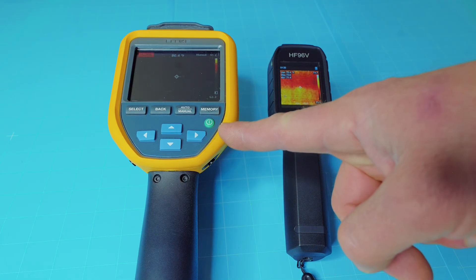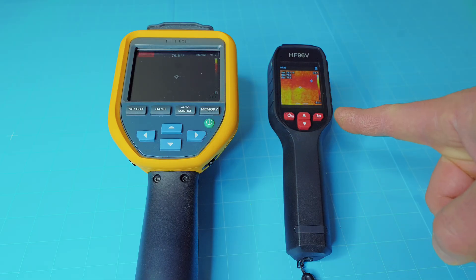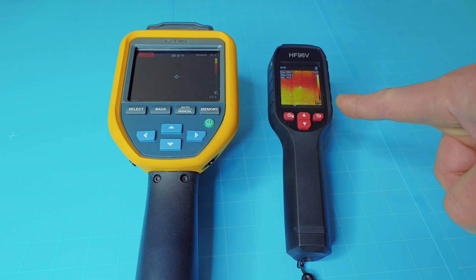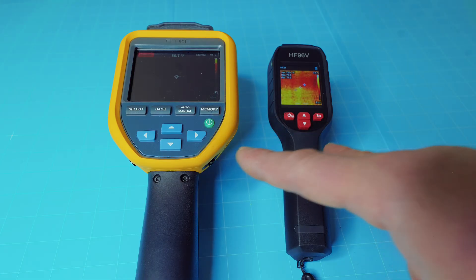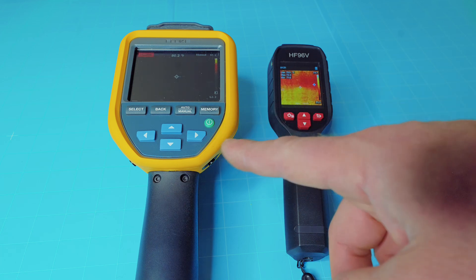Battery life — the Fluke, even though it comes with three batteries, is rated for about five hours depending on which mode you're in. The HF96V battery is rated for eight hours, and I charged it once and this battery is still on full. The Fluke does not have a laser pointer, whereas the HSF Tools does — that's a really handy feature to shoot that laser and know exactly what you're aiming at. As far as palettes, they're both about the same: white hot, black hot, rainbow, iron bow, red hot, and fusion. A few of those modes are named a little bit differently between the two, but they're roundabout the same.